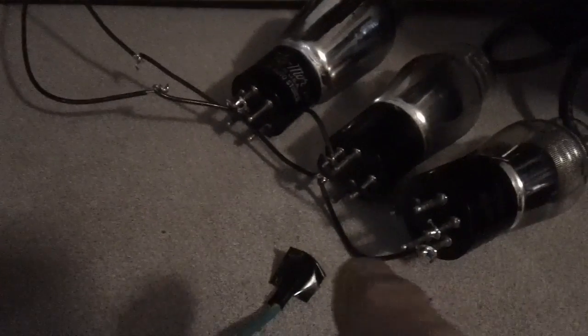When you start pulling on the current, there has to be wire pretty thick to handle it. This thing handles up to 10 amps. We only needed 5, so about half that thickness would have worked, and that's about what we've got with the 14 gauge. Let's see what happens.